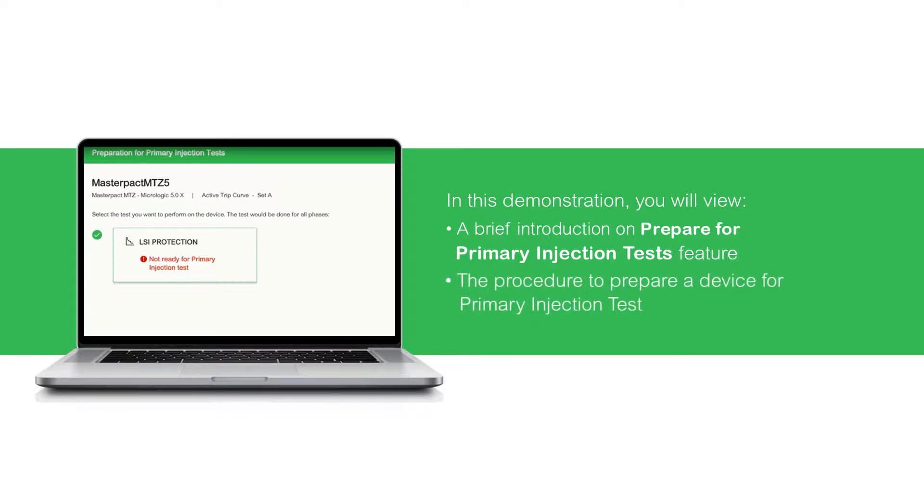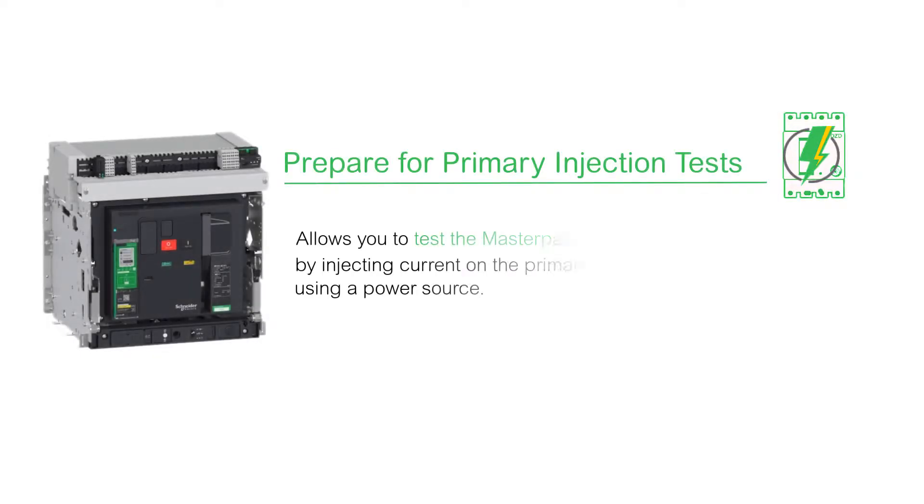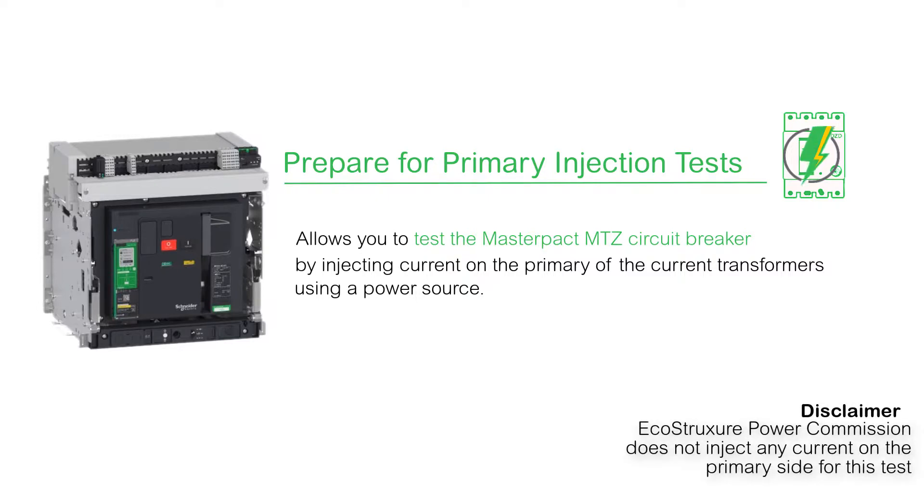The Prepare for Primary Injection Tests feature allows you to test the Masterpact MTZ circuit breaker by injecting current on the primary of the current transformers using a power source. EcoStruxure Power Commission does not inject any current on the primary side for this test.